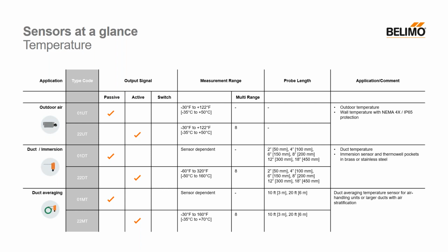It's important to note that when you select a pipe sensor, so say you need an 8-inch pipe sensor for chilled water or hot water applications, you'll have to select a well to go along with it. So our pipe sensors do require a well. It's a separate part. If you use Belimo SELECTPRO to select your valves and actuators, you can also use it to select your sensors. And it will prompt you, it will say, oh, if this is a pipe application, make sure you select a well. And it will direct you to the proper size well for the application. We also have duct averaging sensors in both active and passive styles.